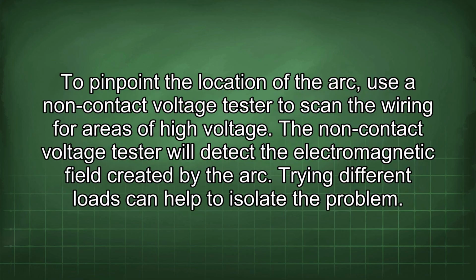To pinpoint the location of the arc, use a non-contact voltage tester to scan the wiring for areas of high voltage. The non-contact voltage tester will detect the electromagnetic field created by the arc.